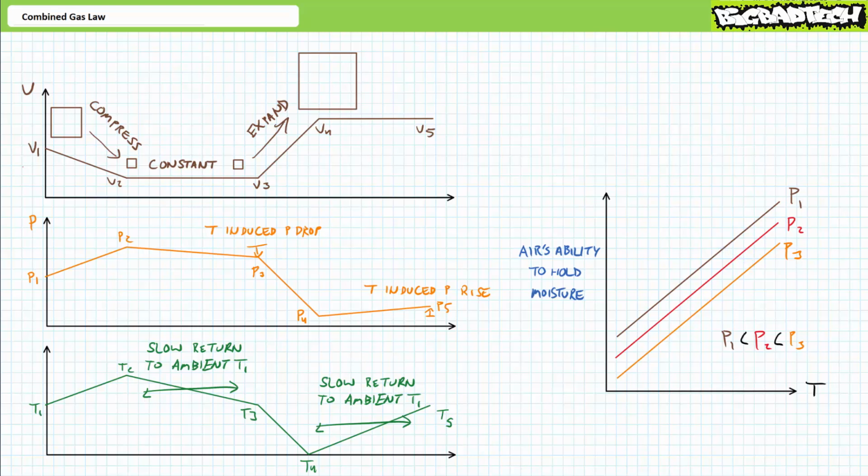Similarly, during a super rapid adiabatic expansion, like opening a dump valve at the end of a workday, one might move from curve P3 to P1, at the same time moving dramatically left along the temperature axis, to find moist air leaving the reservoir at such a reduced temperature it momentarily freezes and blocks the dump valve.